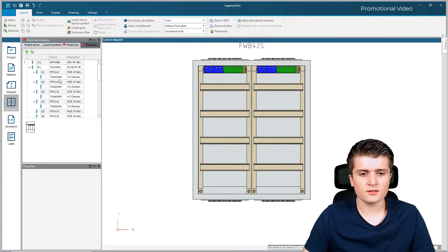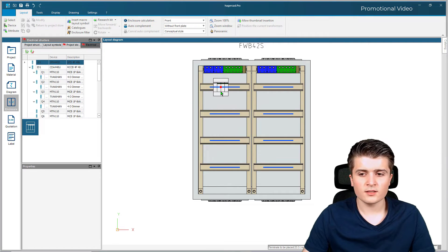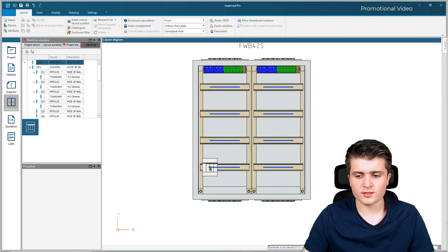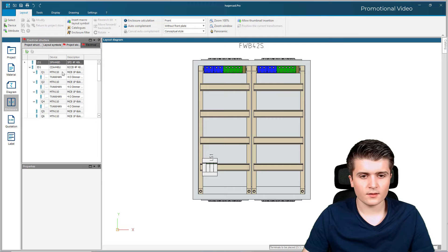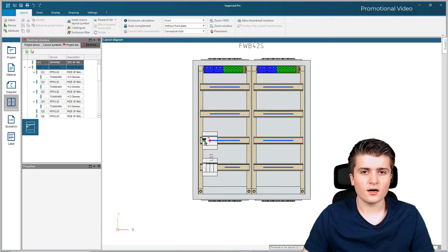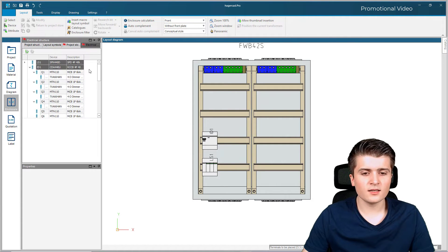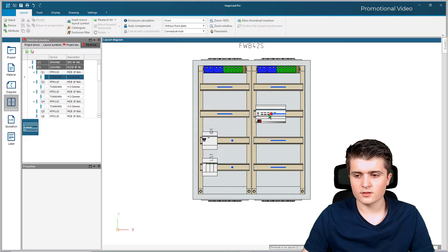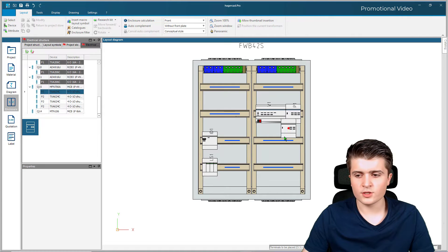Now I can start to place down my devices, starting with the main protective device. I hold it and you can see blue lines marking where we can place it — I want it on the bottom left because my incoming comes from there. Then I place down the RCD, and before placing the circuit breakers I first place down the KNX contacts of the dimmer, the switching actuator, and the shutter actuator below.